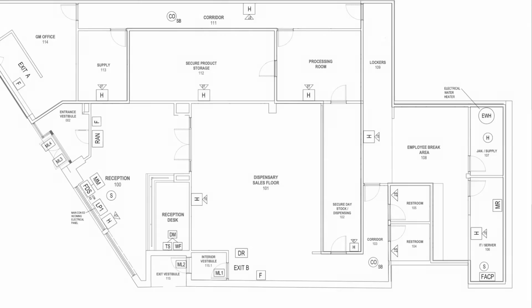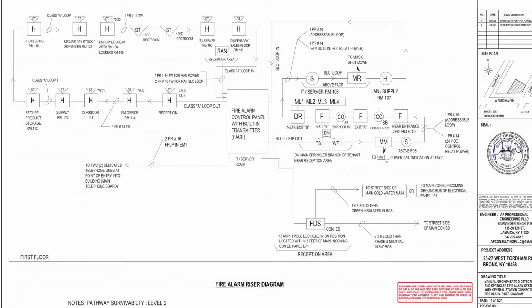After we design the fire alarm system, we have to then fill out a TM1 application. This application is submitted to the fire department along with the fire alarm design, which is actual floor plans of where we're going to put each and every device, and a fire alarm riser diagram, giving them a 1-line diagram of what's actually going in the building and what floors. The final thing, along with supplying the TM1 and a riser diagram, is an ACP5.